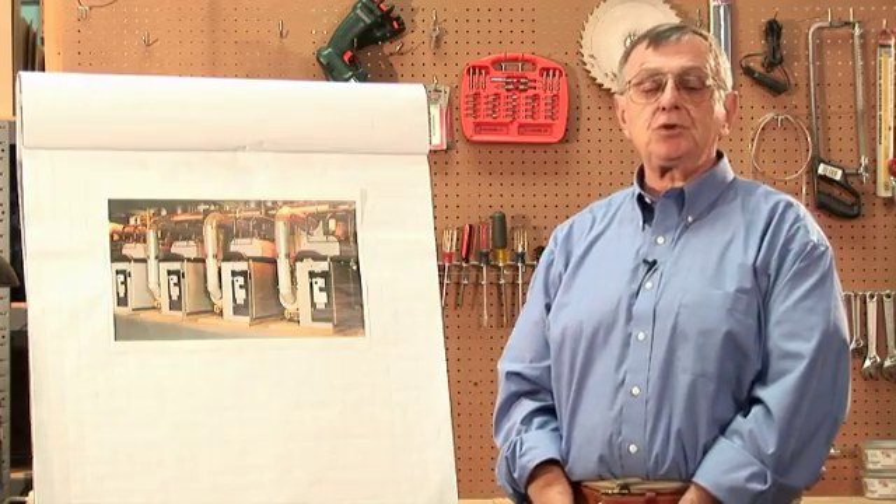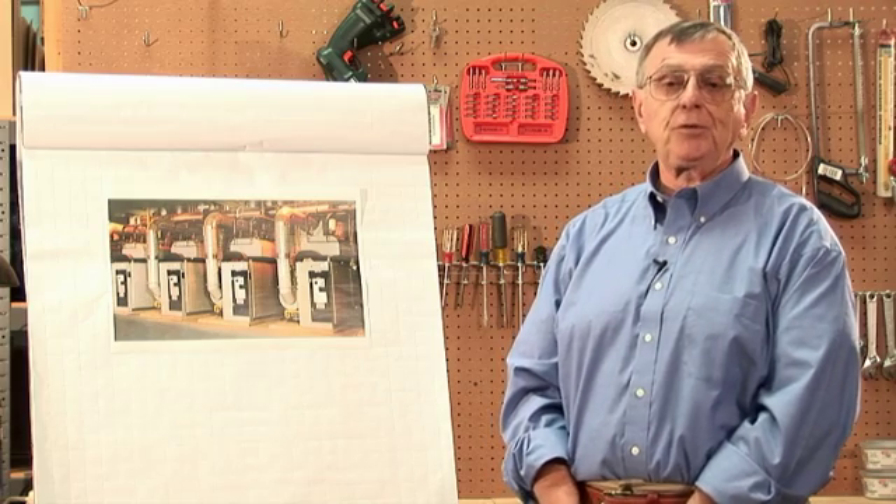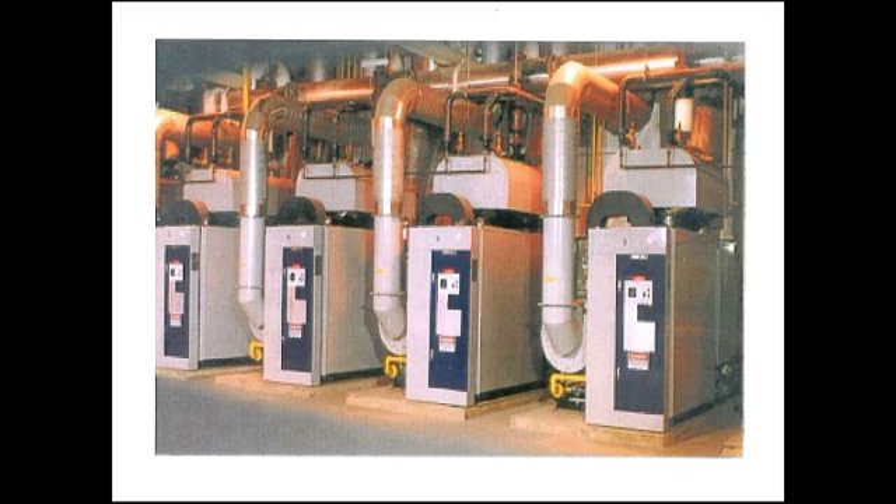Miura boilers, which were designed and engineered in Japan but are now built in North America, were designed with a simple philosophy: the most efficient boiler is one which is not running. So the whole design premise of this boiler is to immediately shut the boiler off the minute there's no steam demand on it, and have the ability to turn the boiler on very quickly — typically about 30 seconds from no boiler in operation to the boiler in operation.